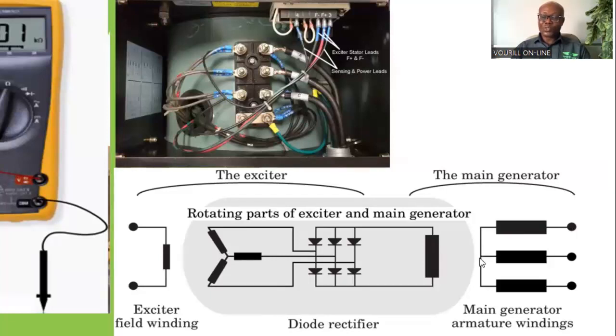When the generator is not working, you take between here and here, you will get the resistance of this winding. Between the neutral and line 2 will give you the resistance of this winding. Between the neutral and line 1 will give you the resistance of this winding. You expect all of them to be equal, since they are the same.